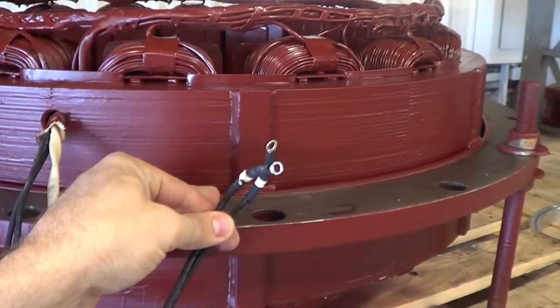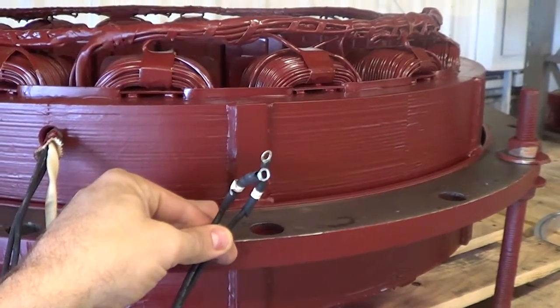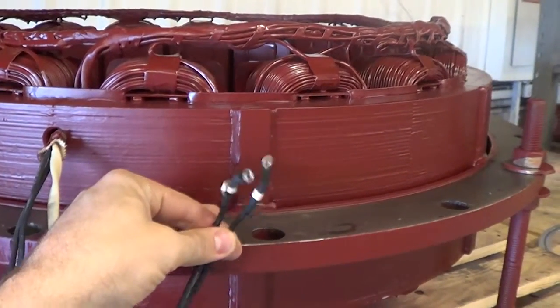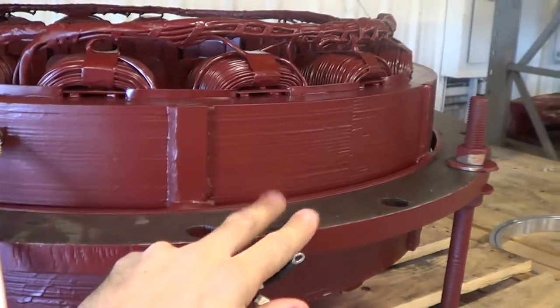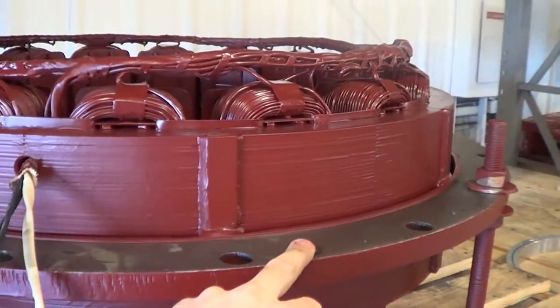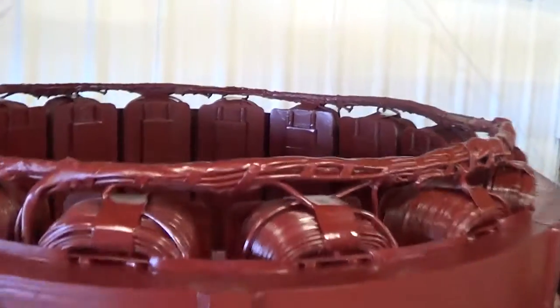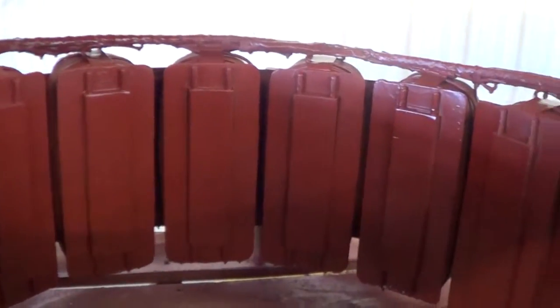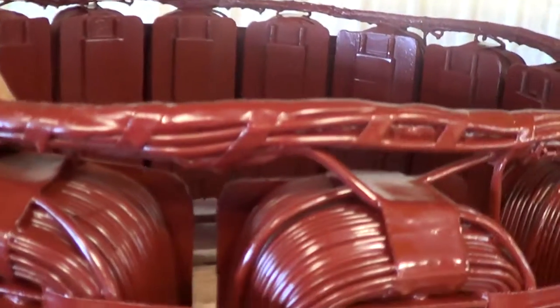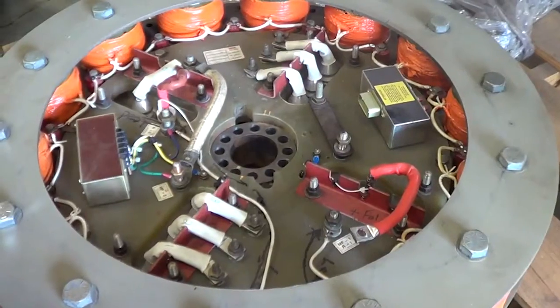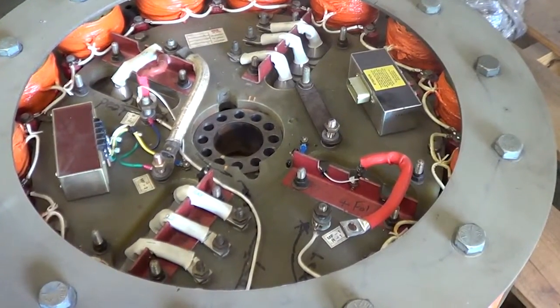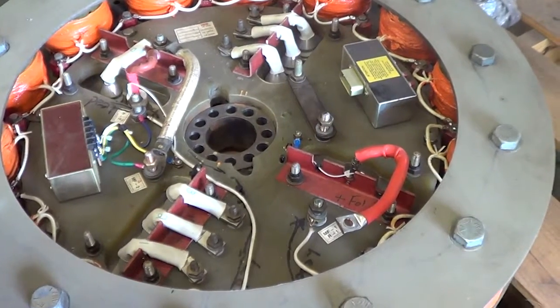Check the resistance across each and record the number in the report, and test the insulation resistance to ground from the 2 cables to a bare metal surface. Record these results in the field report. Perform a careful visual inspection of the inner core for any evidence of contact, as well as the end turns and lashing rings.